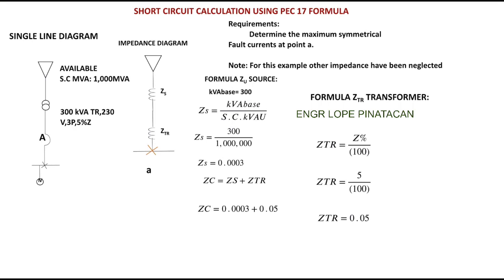So we replace the source impedance with the value of 0.0003 plus the impedance of the transformer, which is 0.05, and then the result is 0.0503. So that is the combined impedance of the circuit. Combined impedance, so this is the transformer impedance 0.05 and the source is 0.0003. So we will add that one, so this is the result, 0.0503. So that is the combined impedance at point a.